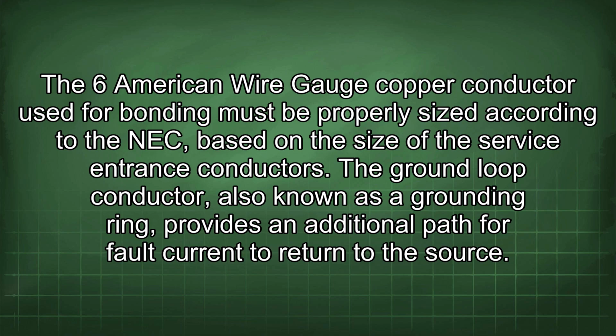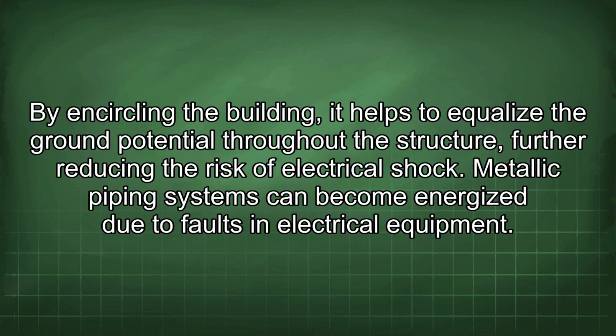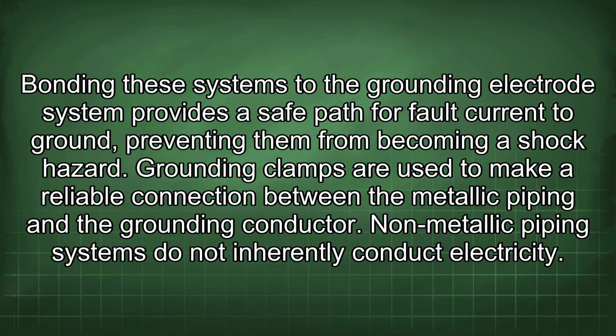The ground loop conductor, also known as a grounding ring, provides an additional path for fault current to return to the source. By encircling the building, it helps to equalize the ground potential throughout the structure, further reducing the risk of electrical shock. Metallic piping systems can become energized due to faults in electrical equipment. Bonding these systems to the grounding electrode system provides a safe path for fault current to ground, preventing them from becoming a shock hazard.